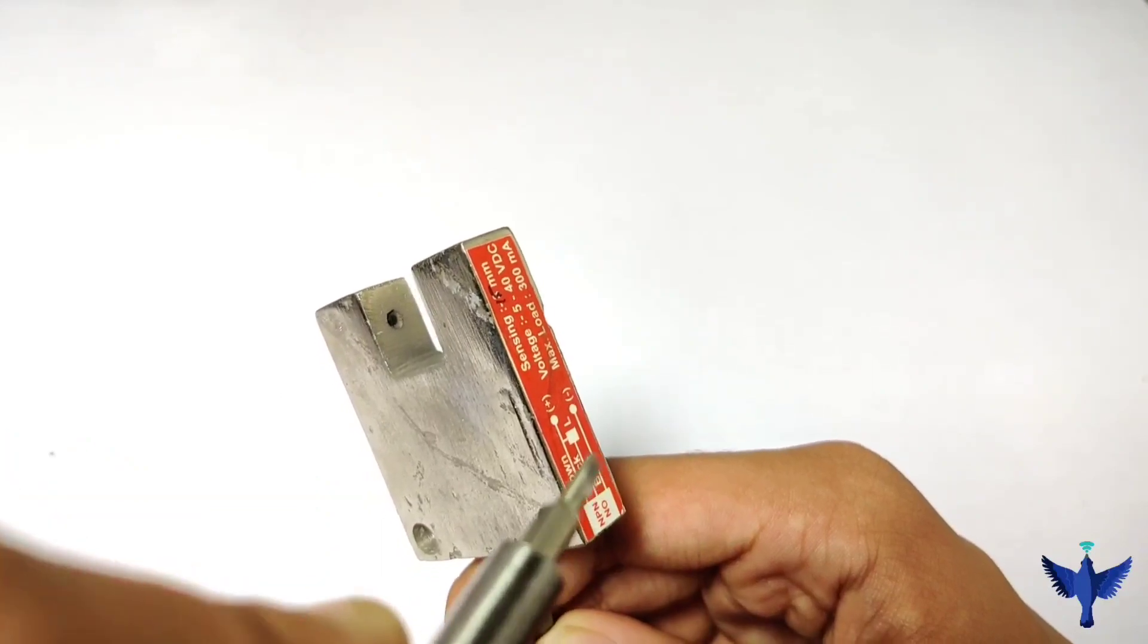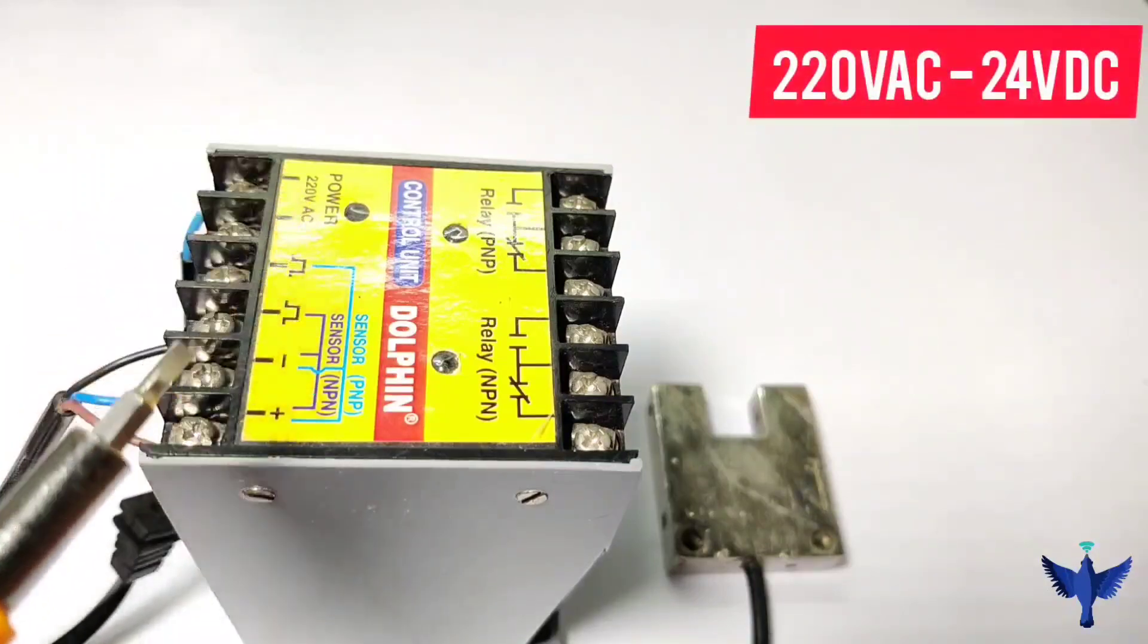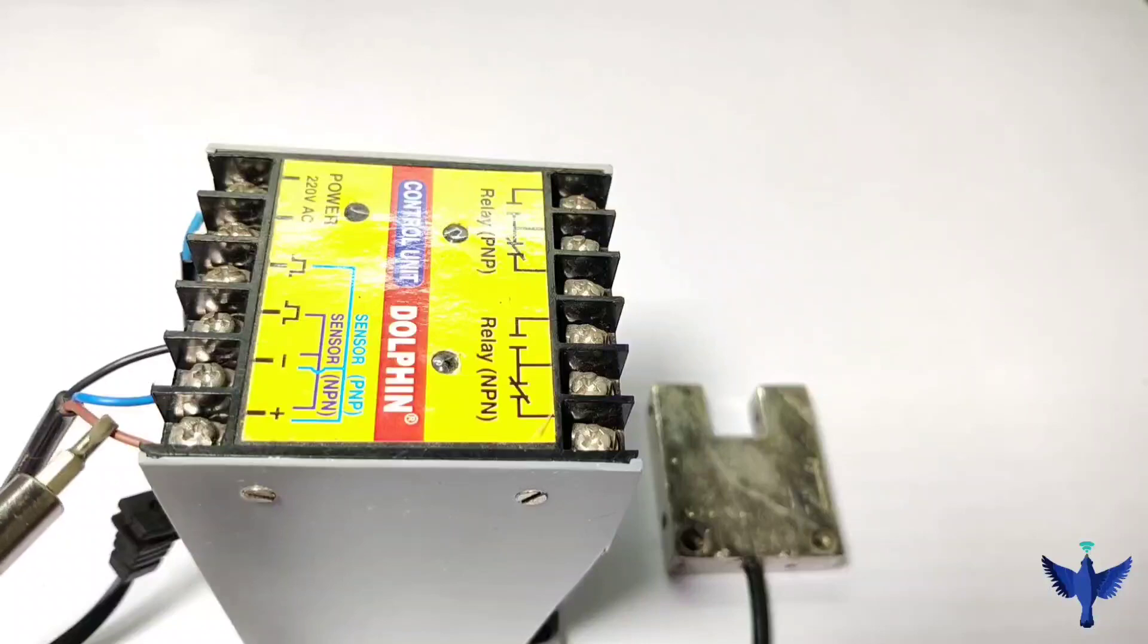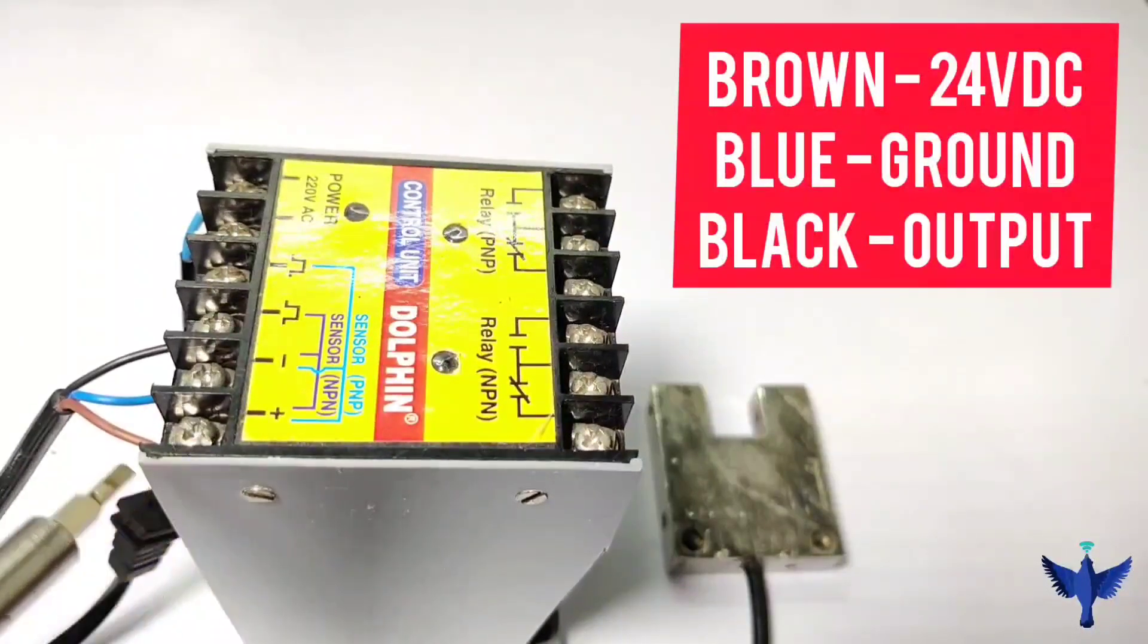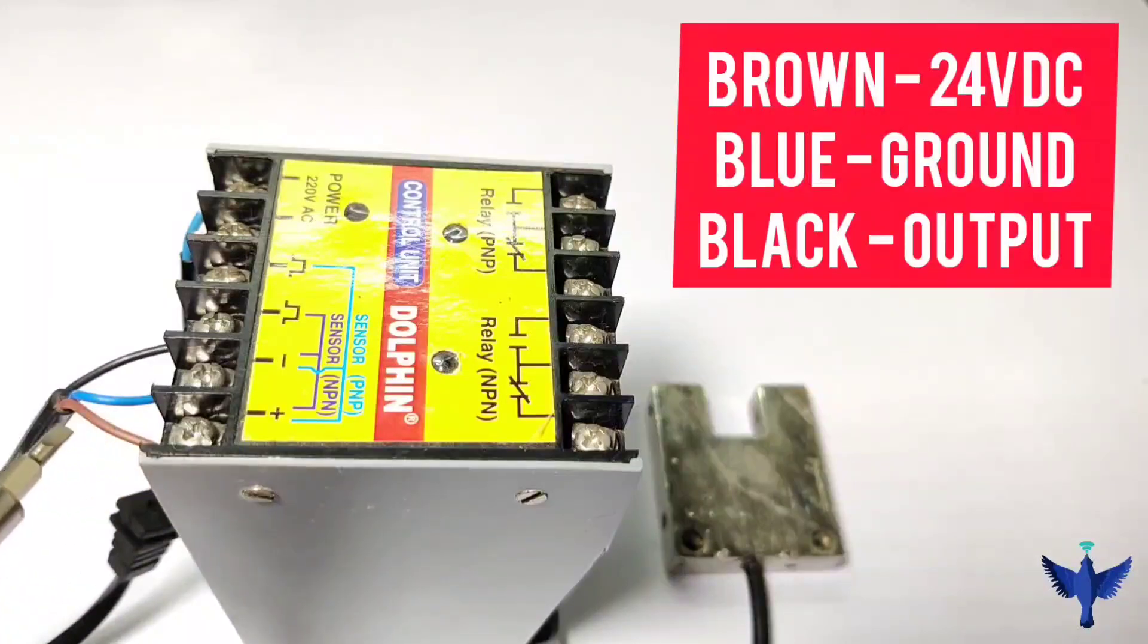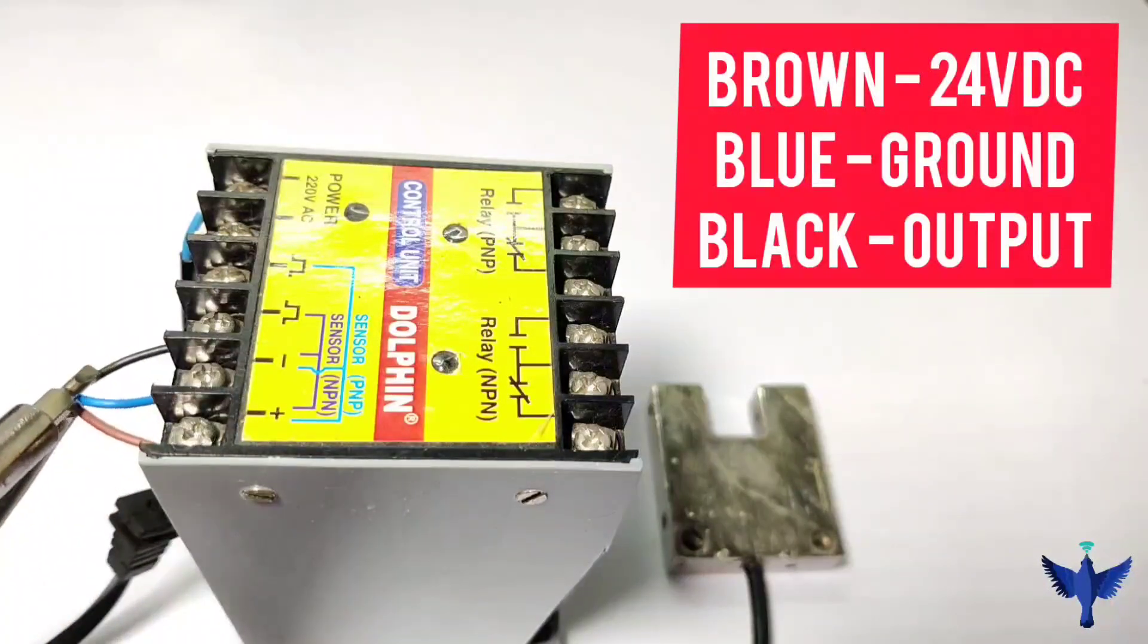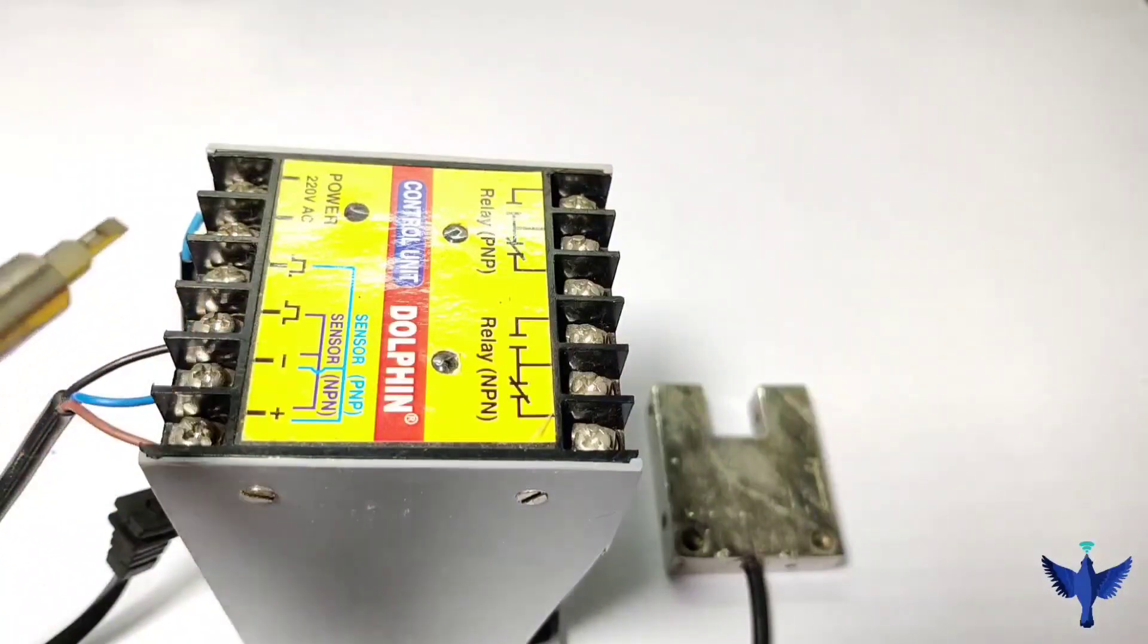Let's have a look at this connection. This is a control unit. It converts 220 volt VAC to 24 volt VDC positive and negative. The output positive wire of the sensor, which is the brown wire, is connected to the positive point 24 volt VDC. Blue wire is the negative wire which is connected to negative point. Black wire is output which is connected to the output and is internally connected to the relay of NPN type.